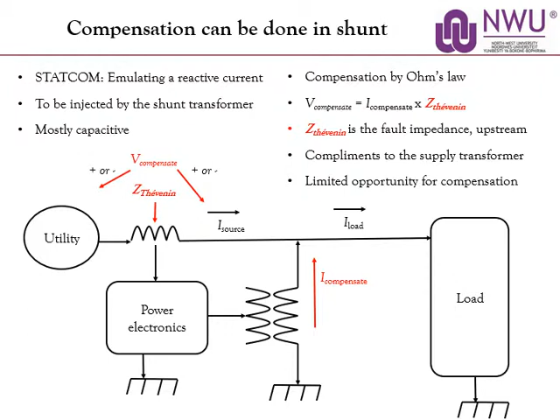Now, why would we like to use such a STATCOM? Yeah, to improve voltage regulation, control power factor, and on long lines to improve the steady-state power transfer capacity or capability, improve transient stability margins between different areas of transmission, different systems, damping subsynchronous power system oscillations, controlling voltage flicker. But you see, it becomes less attractive when mitigating voltage dips and even magnitude and even unbalance, as the upstream impedance changes, the compensation changes. And if we add additional impedance, it requires changes to the protection.